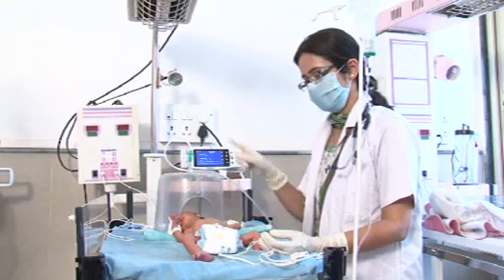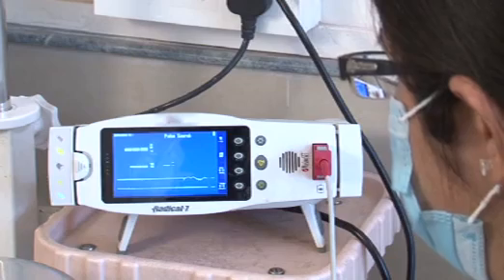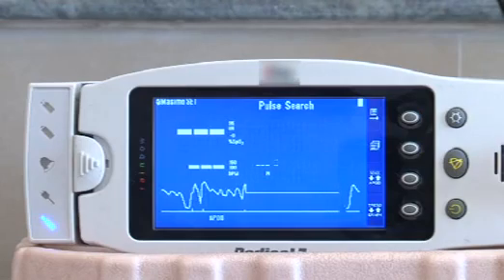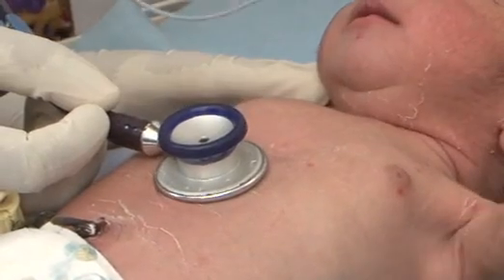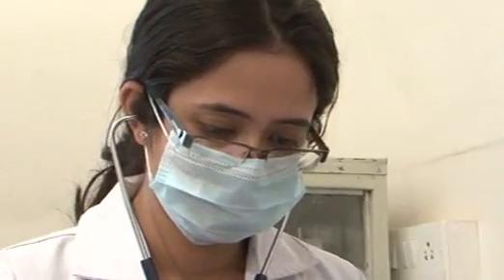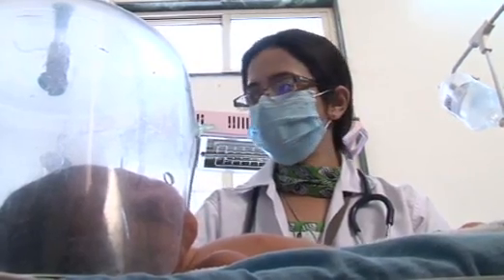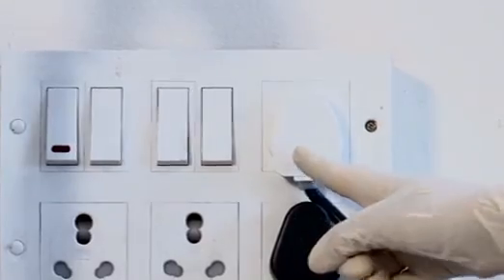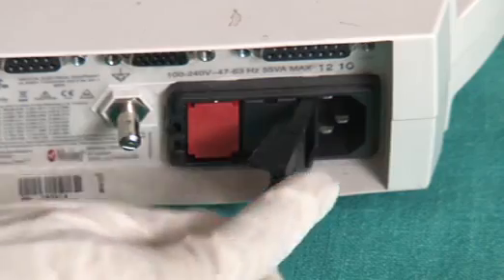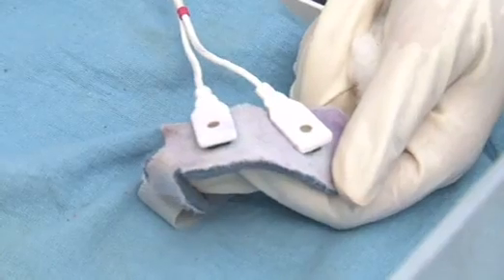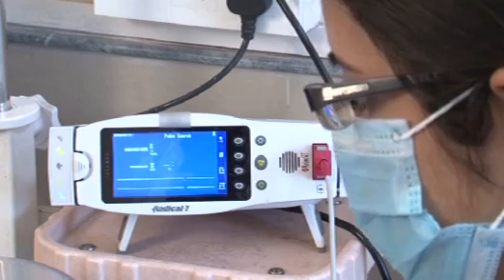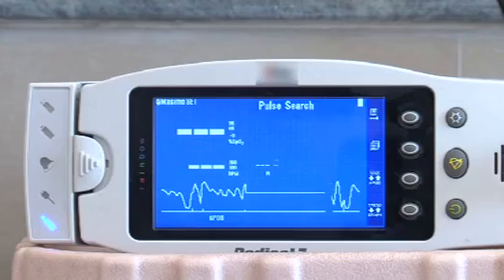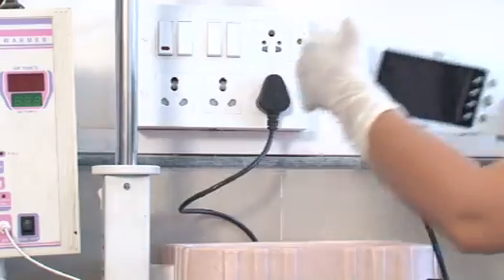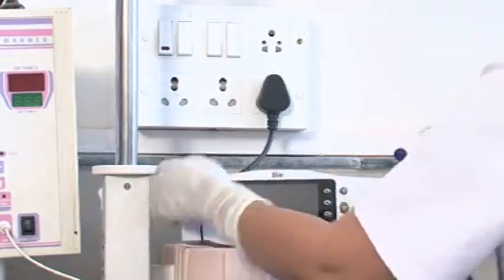Troubleshooting. If there is a failure of the oximeter to display readings quickly, check the newborn. If no deterioration is seen in the newborn, then check plug, battery, fuse, sensor failure and take appropriate action. If it is still not working, use another monitor and get this one repaired.